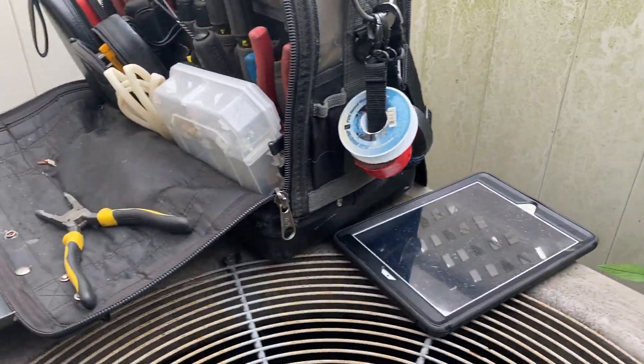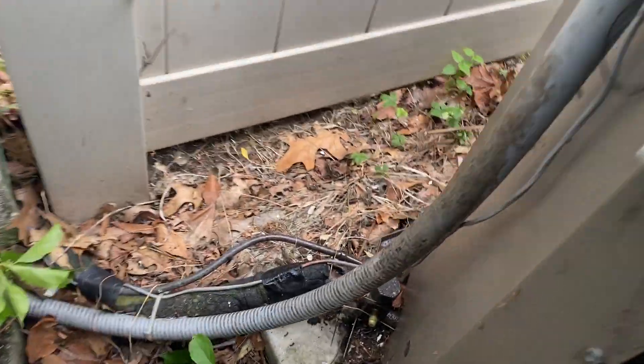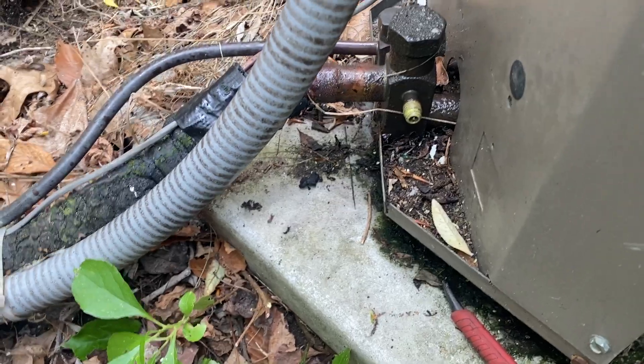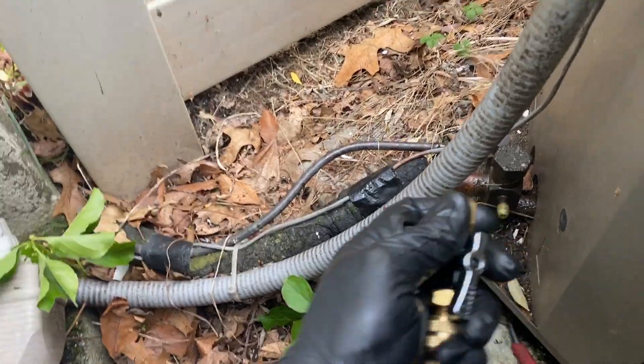I'm not really a good teacher at all, but we just charged up this system with a pound of R22 and what I'm noticing is that the Schrader core right here is leaking. I've got my Appion Schrader core removal tool.